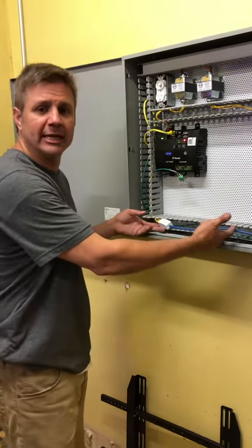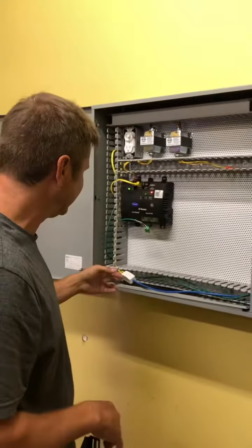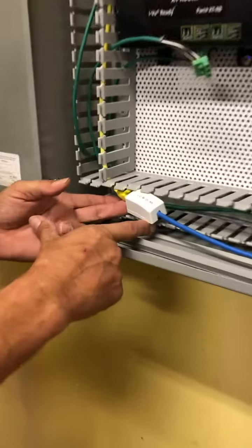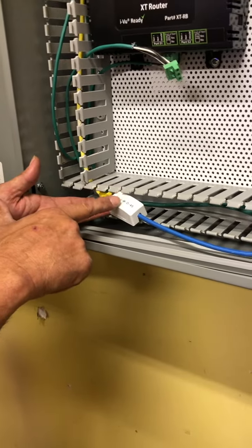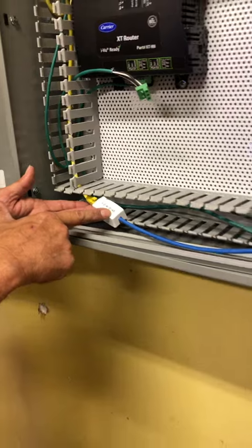What we like to do is bring in the blue cable. This here is the electrical communications head end for an HVAC controller. We went ahead and ran our Cat 6 cable and put a biscuit jack — in this case it's Panduit. We're labeling it site location one, floor two, we're in the MDF, patch panel D, port number 45.